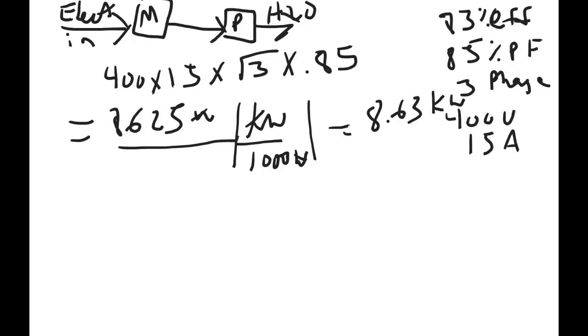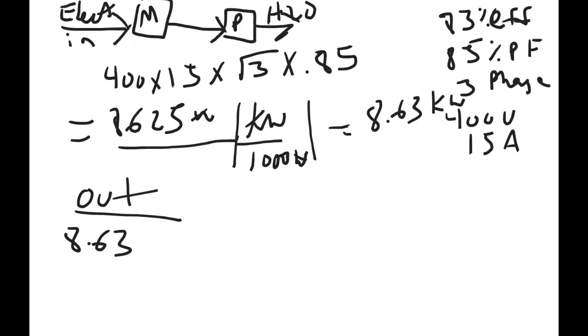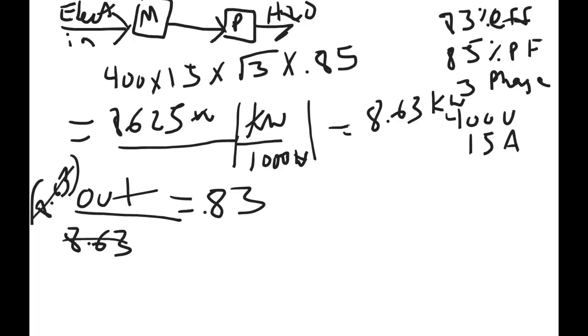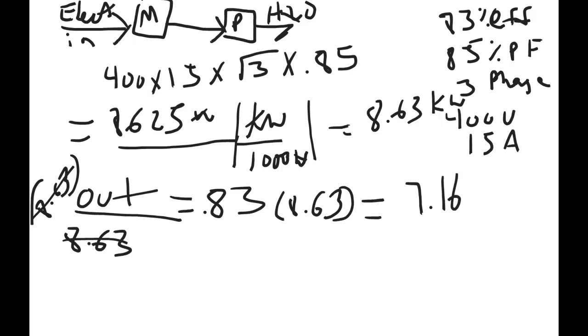Using the efficiency equation, output over input equals efficiency, we can calculate the output of the motor. So we know the input, 8.63, output's unknown, and 83% efficient motor. So multiplying both sides by the input, that gives us 7.16 kilowatts coming out of the motor as output.